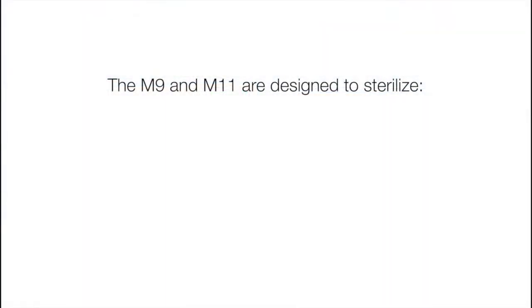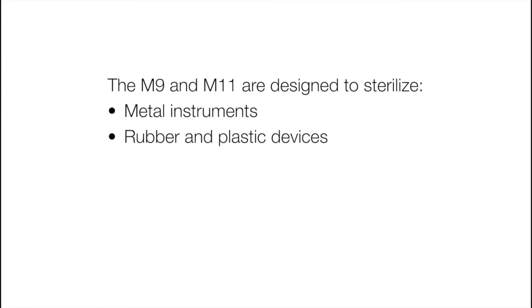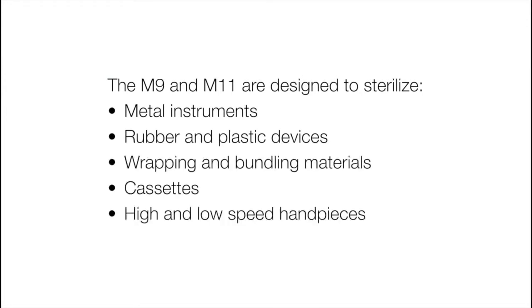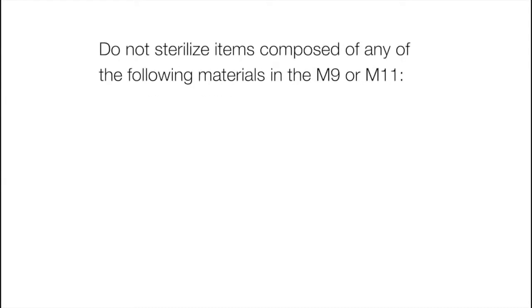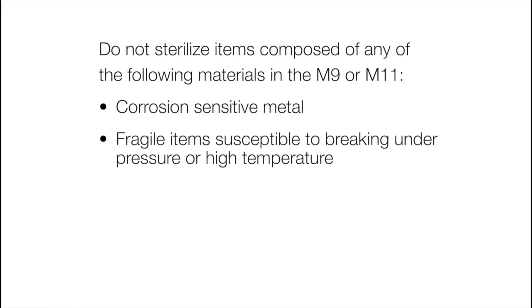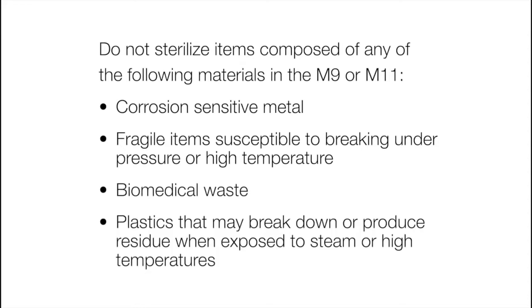The M9 and M11 are designed to sterilize metal instruments, rubber and plastic devices, wrapping and bundling materials, cassettes, high and low-speed handpieces, surgical instruments. Do not sterilize items composed of any of the following materials in the M9 or M11. Corrosion-sensitive metal, fragile items susceptible to breaking under pressure or high temperature, biomedical waste, plastics that may break down or produce residue when exposed to steam or high temperatures.